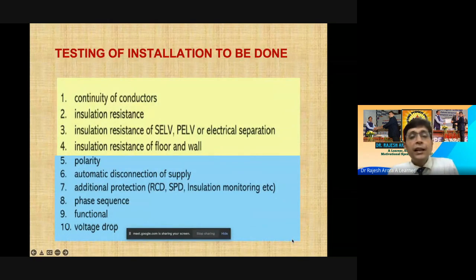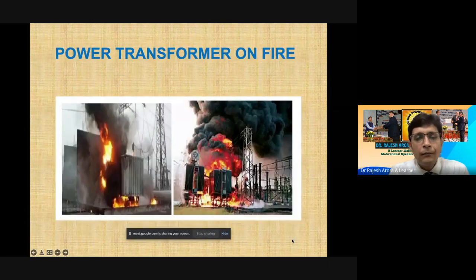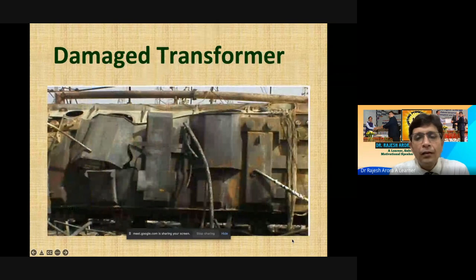All testings at the installation are to be done. That includes continuity of conductor, insulation resistance of SELV, PELV, or electrical separation, insulation resistance of floor and wall. Polarity you have to check. You have to check phase sequence, additional protection, voltage drop. All these tests to be performed as per IS 732. This is a picture showing the fire in a power transformer. These are the pictures of a damaged transformer.